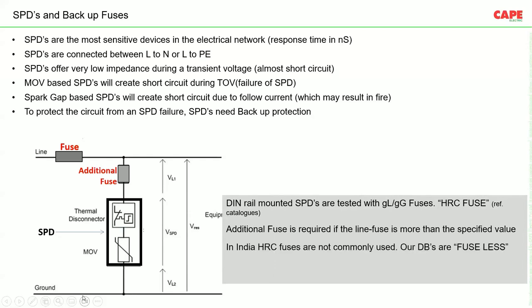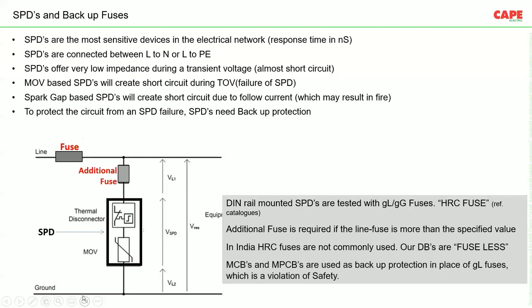In India, there is a preference for fuseless DBs, so people often use MCBs instead of fuses. Some manufacturers also recommend MCBs or MPCBs, which is not safe at all. This is a violation of safety and can cause a fire hazard because fuses and MCBs have completely different tripping characteristics and tripping curves. A 63 A fuse will not trip in the same time as a 63 A MCB, so we must be very careful when choosing backup protection.